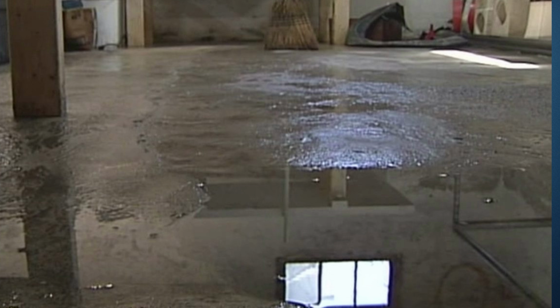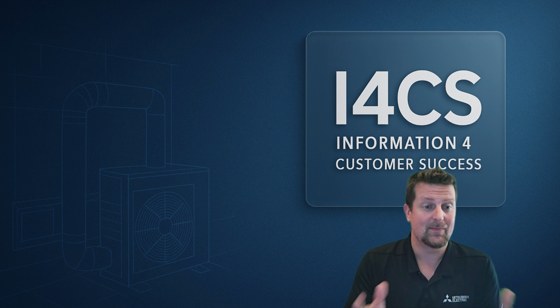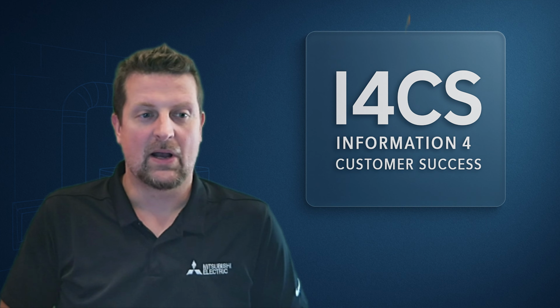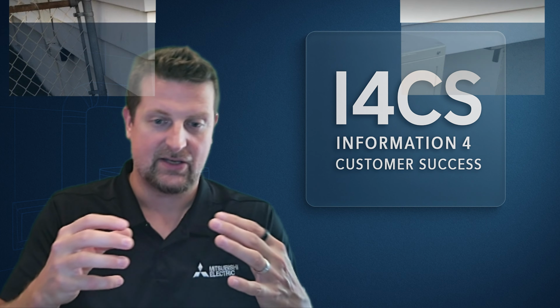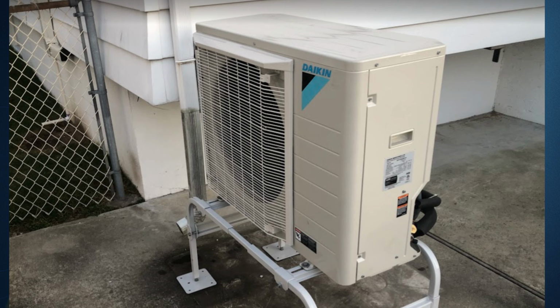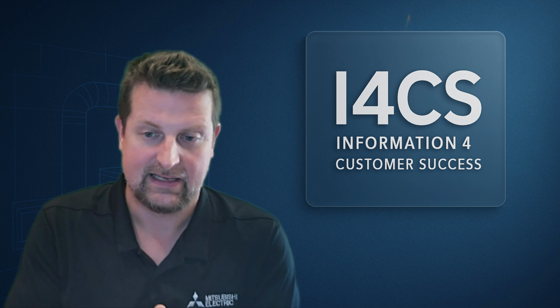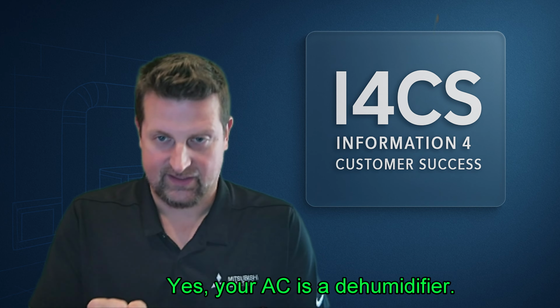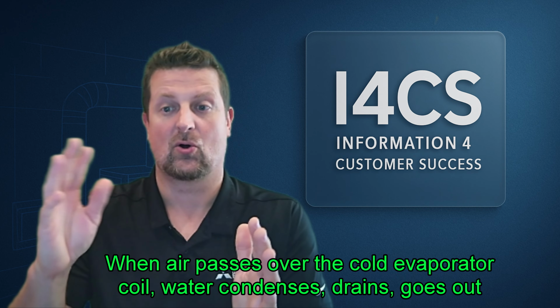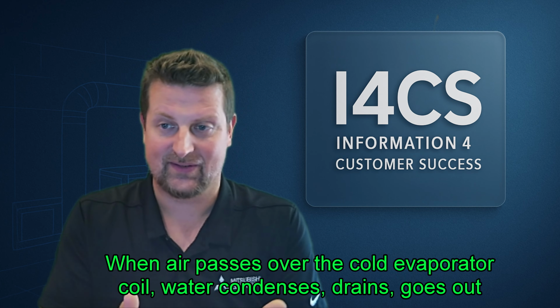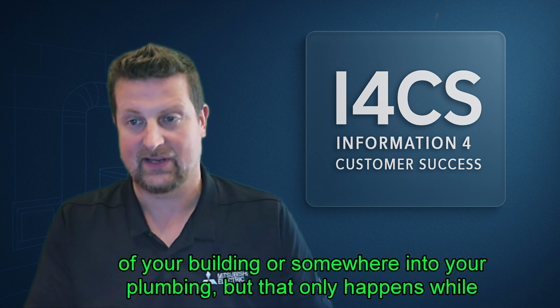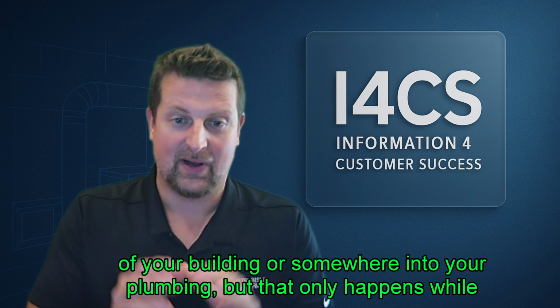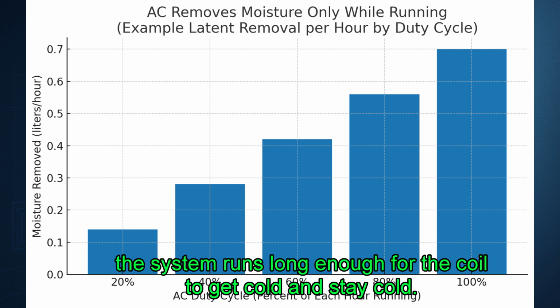But let's just say you fix all that, there's still going to be obviously humidity in the house. So what takes care of the humidity? I know everyone's heard a lot about the dehumidification abilities of different air conditioning systems and how important it is to size your air conditioning system so it's able to dehumidify well. That's absolutely true. Yes, your AC is a dehumidifier. When air passes over the cold evaporator coil, water condenses, drains, goes out of your building or somewhere into your plumbing. But that only happens while the system runs long enough for the coil to get cold and stay cold.